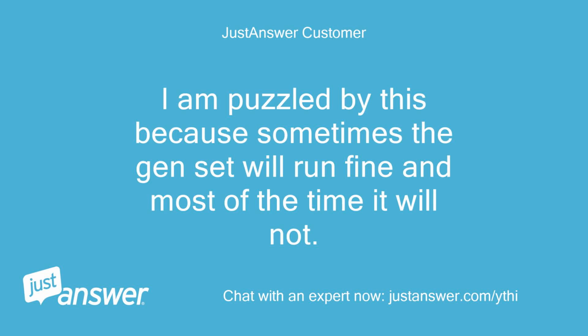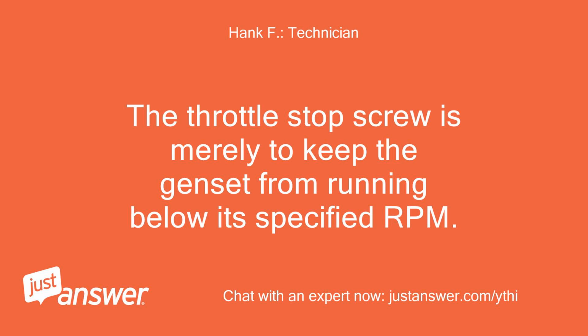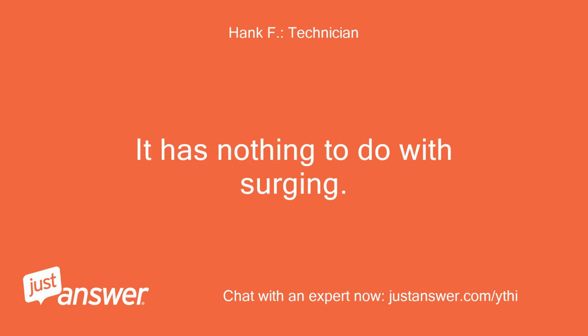I am puzzled by this because sometimes the genset will run fine and most of the time it will not. The throttle stop screw is merely to keep the genset from running below its specified RPM. It has nothing to do with surging.